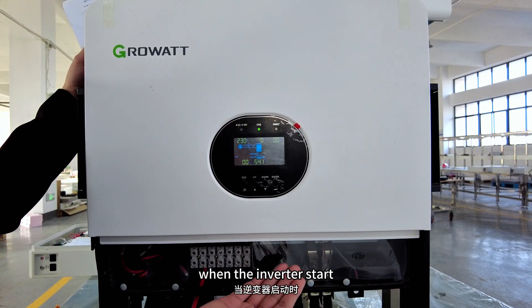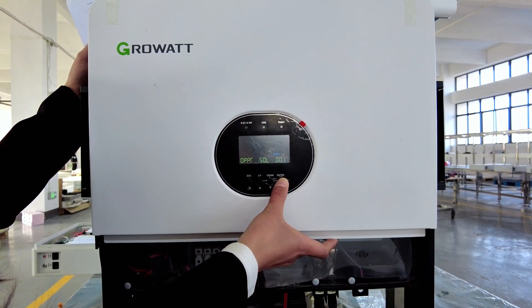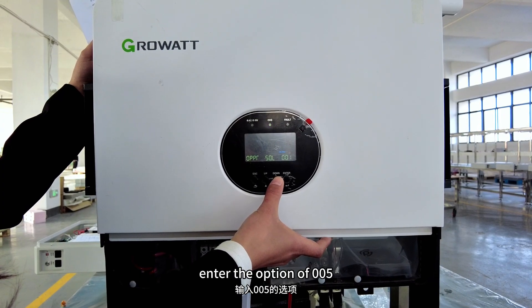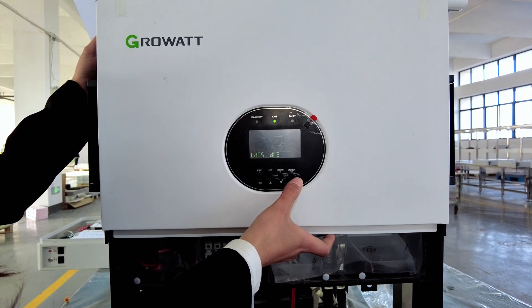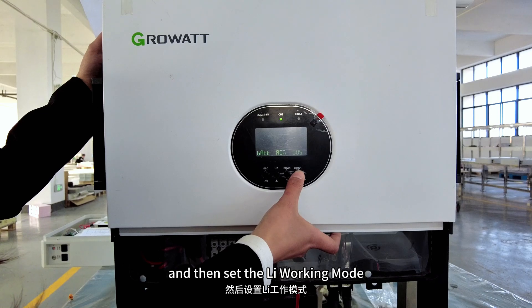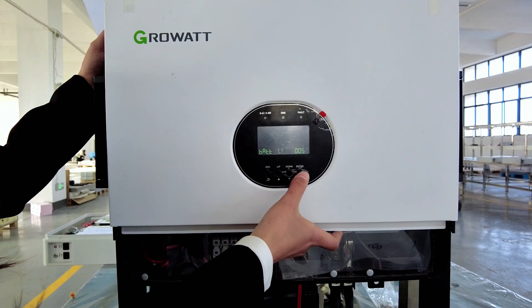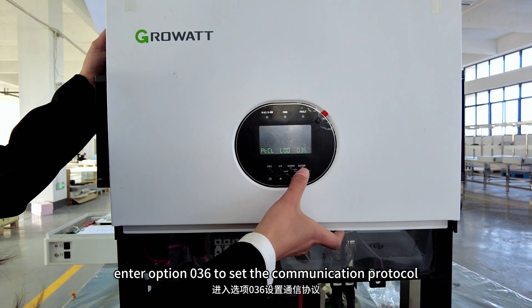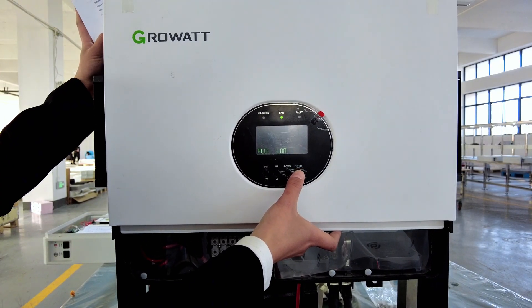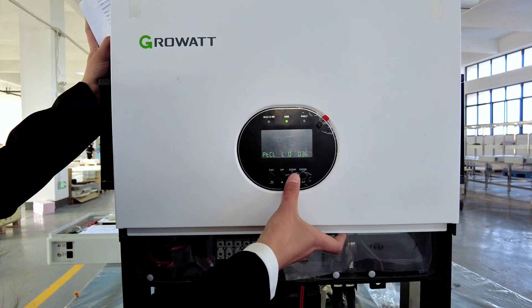When the inverter starts, don't press the enter button. Enter the option 005. Then go to option 036 to set the communication protocol, and select protocol 52.